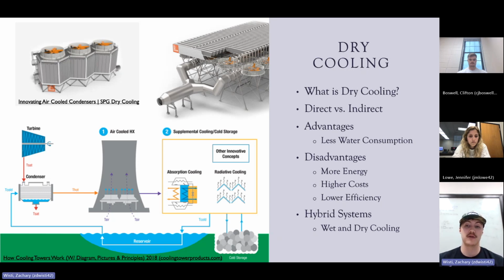The advantages of dry cooling are less water consumption. In direct dry cooling, there's no water consumption, and in indirect, there's a very small amount of water consumption. The disadvantages of dry cooling are more energy, higher cost, and lower efficiency, due to the cooling rate of air versus water. Some plants use hybrid systems where in hot times of the year they use wet cooling, and in cold times of the year they use dry cooling, so they adapt to the changes of the temperatures.